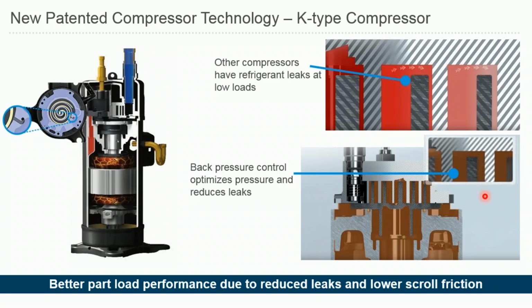And at low load situations, you will start to see more pressure imbalances happening between these two pieces, and this will start causing this gap to widen. When that happens, typically, if you don't have a back pressure control mechanism like we have in our compressor design, you'll see more refrigerant leakage and less efficiency out of your compressor.